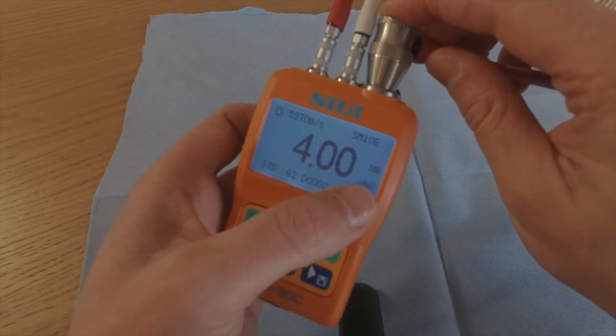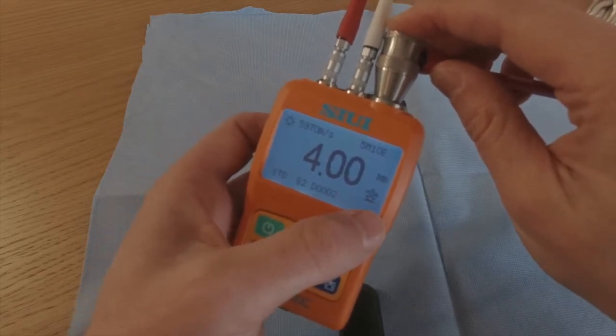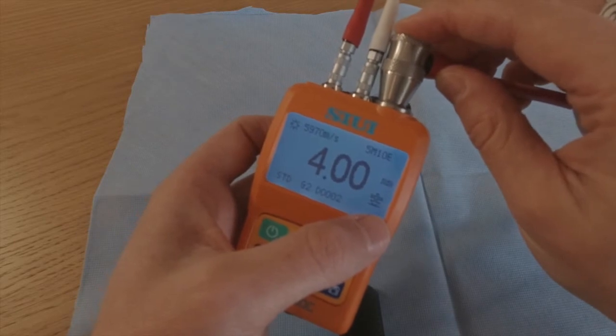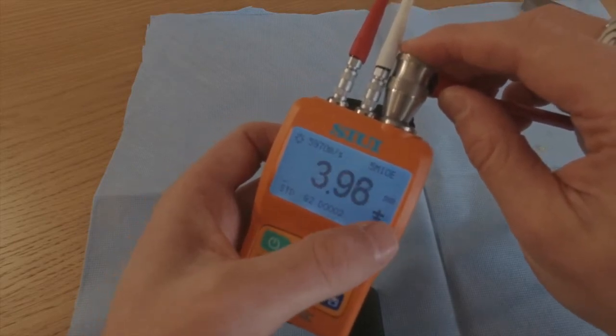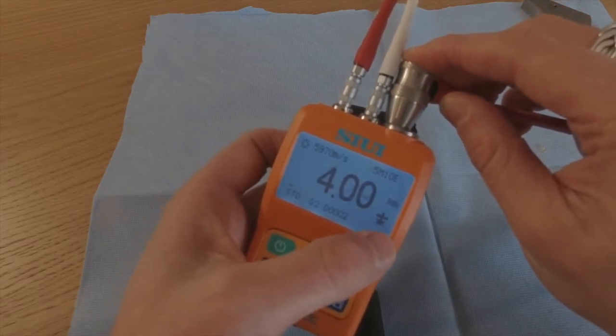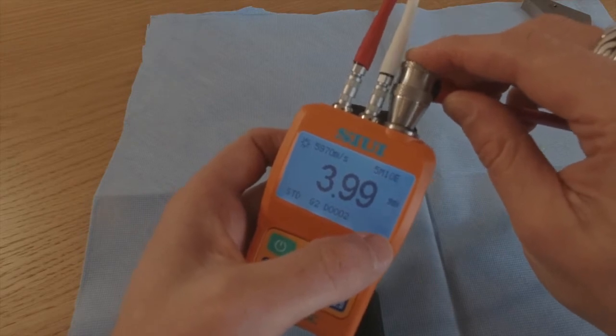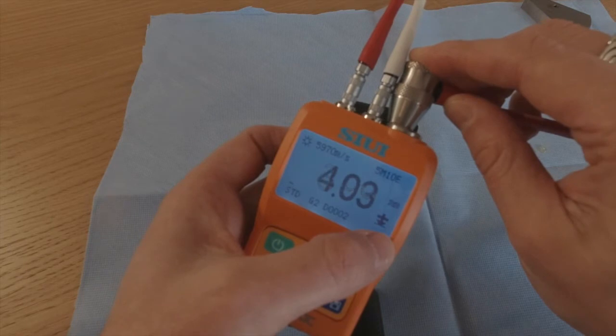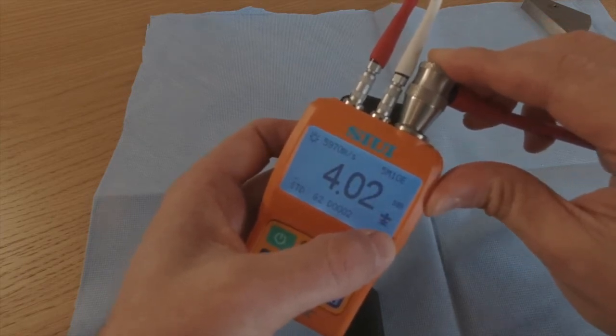Here's a couple of things that you'll notice. Other than the number, what's happening here is I'm not pushing very hard right now. You can see this arrow and it's saying okay, we've got some sort of reading but not very good. But once we put it down and there is good contact and good sound signal, you'll see that it transitioned from an outline to a fully solid arrow pointing down. That's what you're looking for to make sure that your readings are nice and consistent.